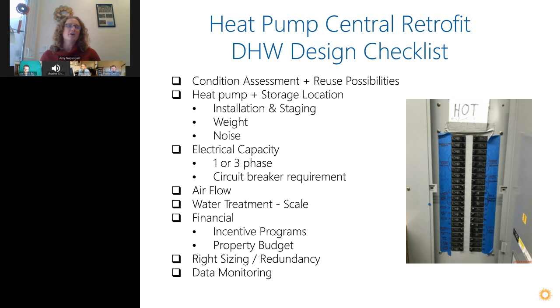The electrical capacity here was a bit of a challenge in that our panel box was fully subscribed, but we had to reorganize all of the circuits in order to put a 90 amp breaker in there for the heat pump. We also talked about the airflow, and water treatment is very important.